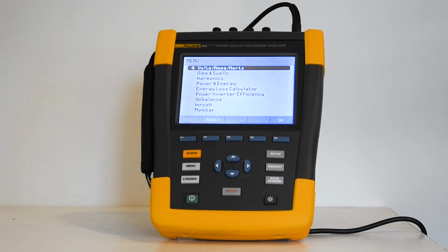Press F2 and select Trend Setup screen. This permits the user to adjust the duration of automatic trend recording. The default is 7 days. Press F4 and select Defaults for the motor setup screen. This permits the user to set the default values defined in the Function Preferences screen, included in the unit setup. The defaults depend upon the motor frequency. Press F5 to start measurements. This starts the motor analyzer function.